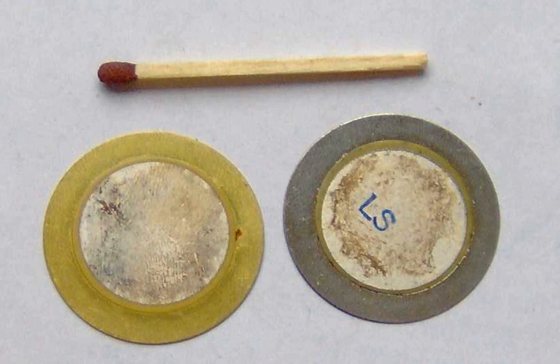The less sensitive natural single crystal materials — gallium phosphate, quartz, and tourmaline — have a higher, and when carefully handled, almost unlimited long-term stability. There are also new single crystal materials commercially available, such as lead magnesium niobate-lead titanate (PMN-PT). These materials offer improved sensitivity over PZT but have a lower maximum operating temperature and are currently more expensive to manufacture.